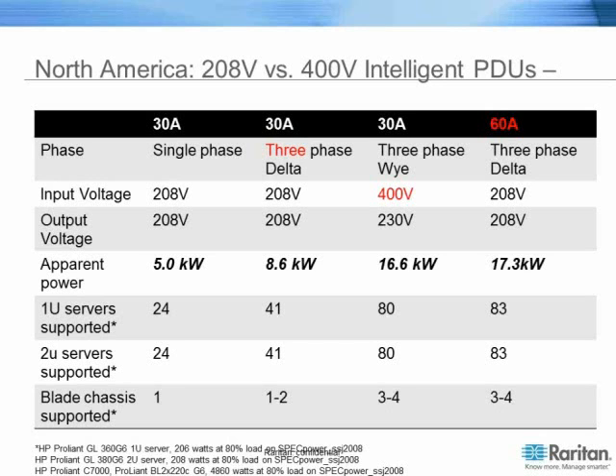This is having that talk with customers, going from 208 into 3-phase. We're going from 5 to 8.6. Now we can almost double the amount of servers we can bring into that rack. But once we bring in that 3-phase equivalent, there's some interesting comparison here.